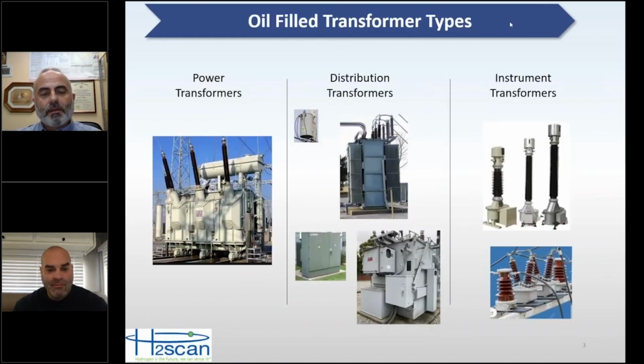So there are lots of different types of oil-filled transformers. There are other types of transformers, dry types and so forth, but if you're going to be looking at online monitoring of transformers, most of the time, well, DGA anyway, and hydrogen monitoring, there's going to be some type of oil inside. And when there's a problem in the transformer and things start heating up, that oil starts degrading, and hydrogen is a byproduct of that oil degradation, usually due to high temperature. So when bad things happen in transformers, that's when you start generating hydrogen.